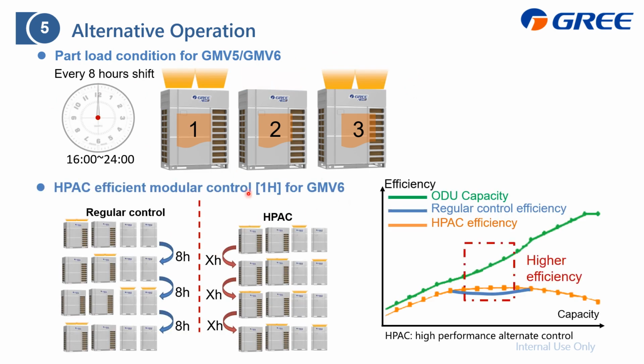For GMV6, we have this HPAC, or high performance alternate control. Compared with the regular control, which shifts every 8 hours, the shift time is not fixed. It can dynamically adjust according to the system load. On the other hand, you can find that it always chooses the high performance outdoor unit to ensure the system performance. From this diagram, you can find that the green color is the outdoor unit capacity output, according to the indoor unit. And this orange line is the efficiency.